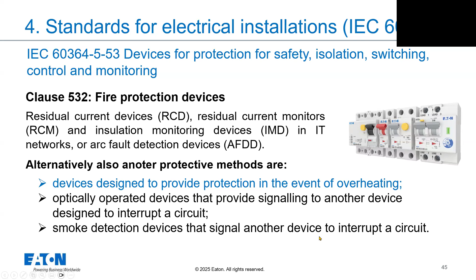And here we have one solution which Eaton has offered for many years, advanced fire protection. It's a so-called diagnose system, a thermal monitoring system for low voltage switchboards. And the advantage is that this system is monitoring 24 hours, 7 days a week, and our system is working with wireless sensors. Wireless sensors are on this picture on the right side down.